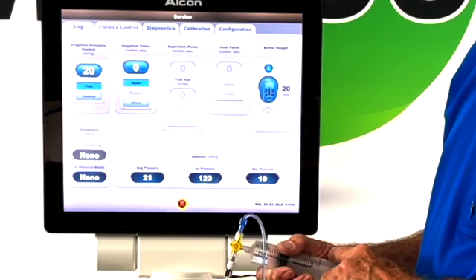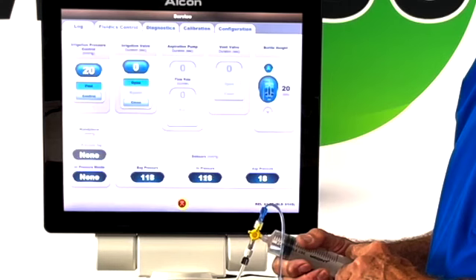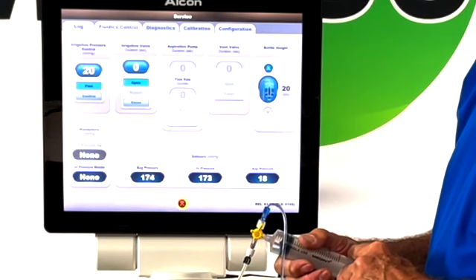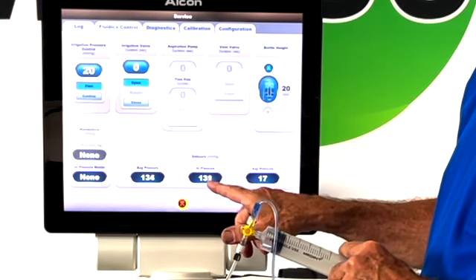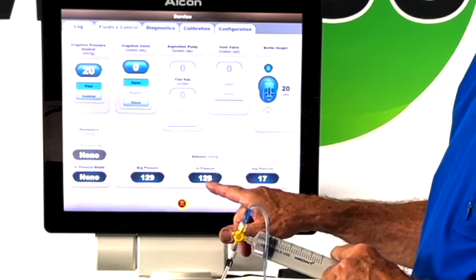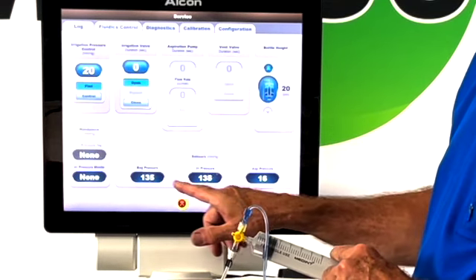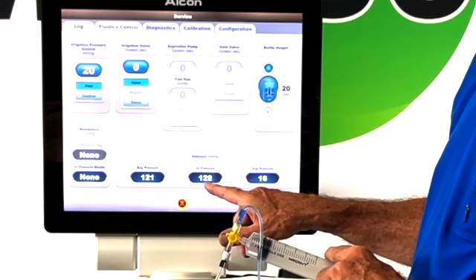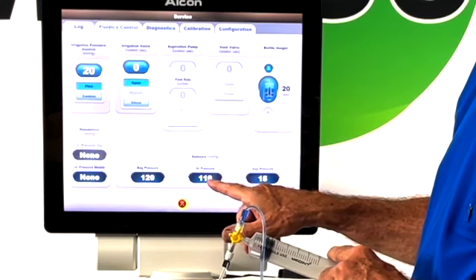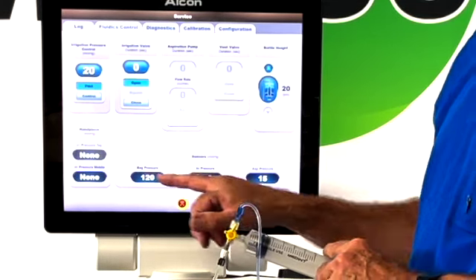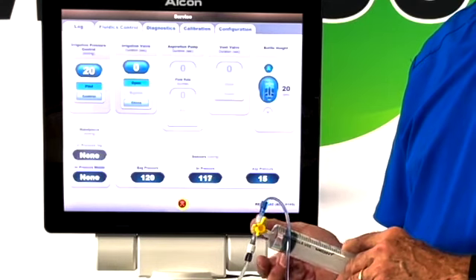So as I increase the pressure, so we want it at 120. There's roughly 120 right there, and we have 130. Well, let's come back a little bit. 118, 119, 120. Very close. So the bag pressure sensor at 120 is working.